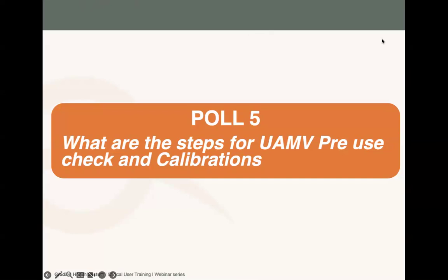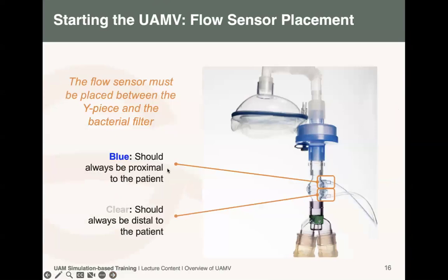So, as I said before, during the training we always emphasize the machine check, whereby we check the machine in general: the brakes, the cleanliness, oxygen analyzer, concentrator, power, all of those. But we also do the UAMV, so today we discuss more of the UAMV part of it. Among the other things, the most important thing is to make sure it's well connected and well attached. It's the flow sensor. You have to make sure the flow sensor is available.